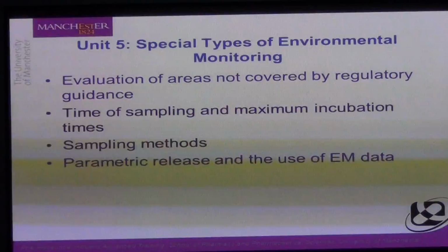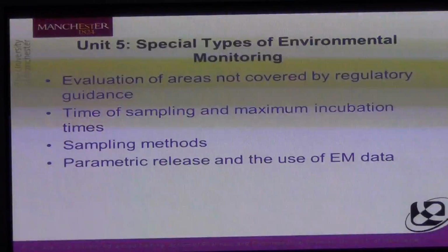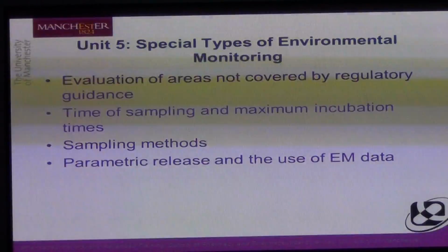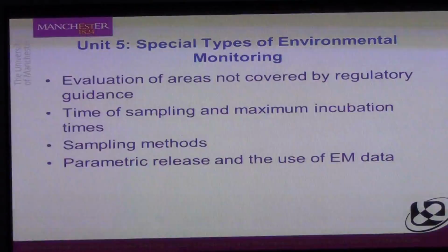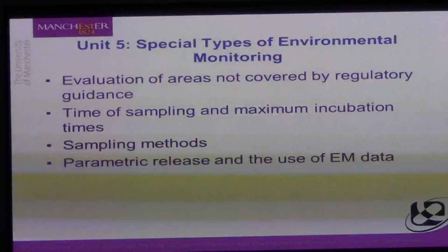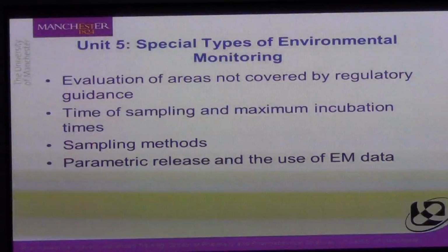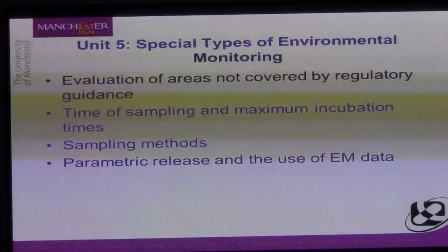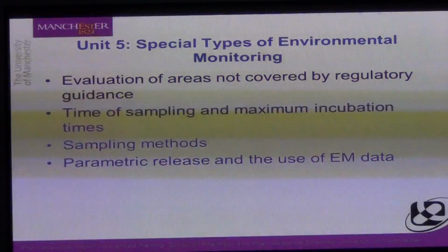Now, parametric release is something which is applied to terminally sterilised products in lieu of sterility testing. And here, environmental monitoring data informs us as to whether or not we can release a terminally sterilised product.